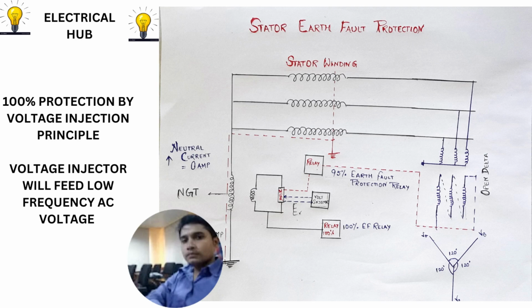So, how is it protected? It is protected by the voltage injection principle. What is the voltage injection principle? The voltage injector will inject a low frequency AC voltage through the secondary side of the NGT to the primary, and then it will go into the winding. But since it is a very low frequency AC voltage, it will not create any problem. Why? We will discuss.